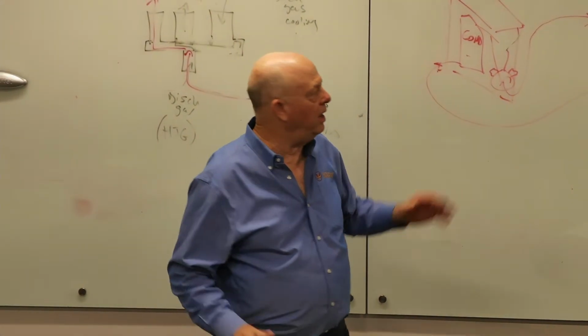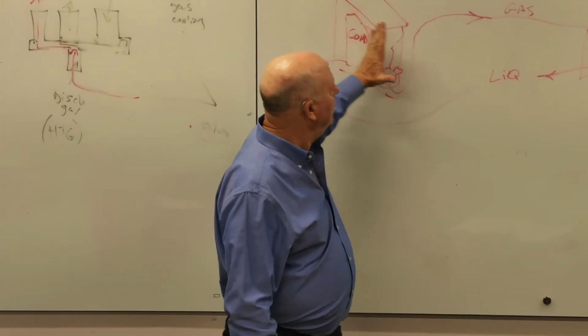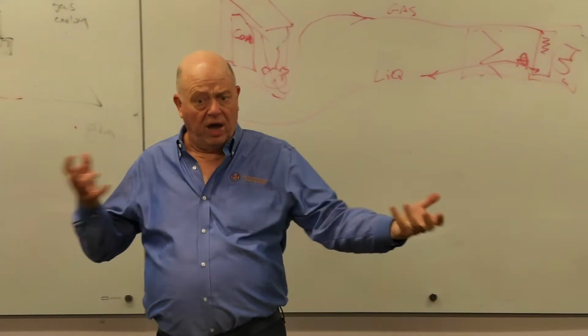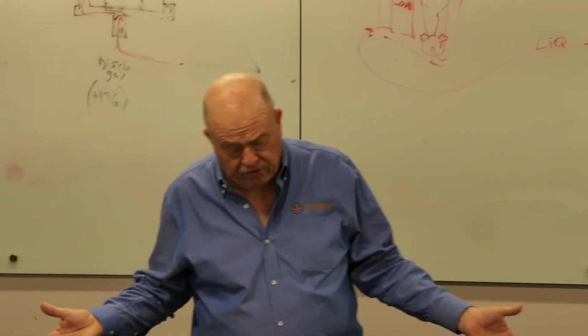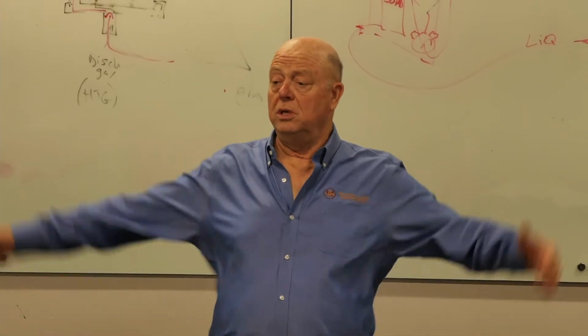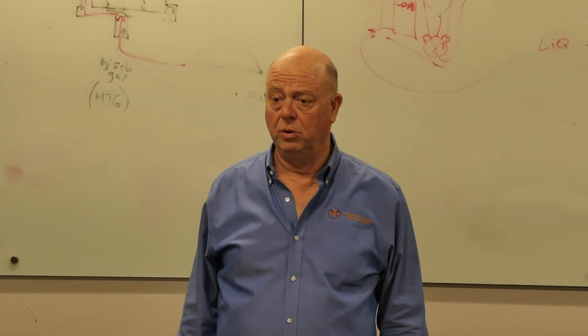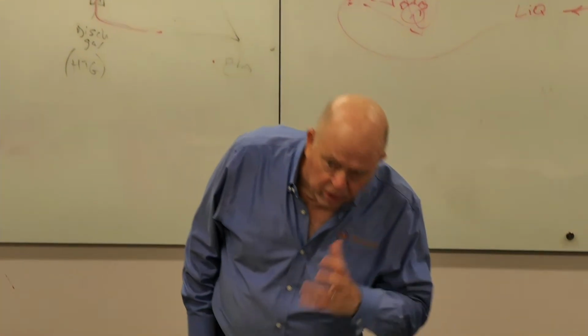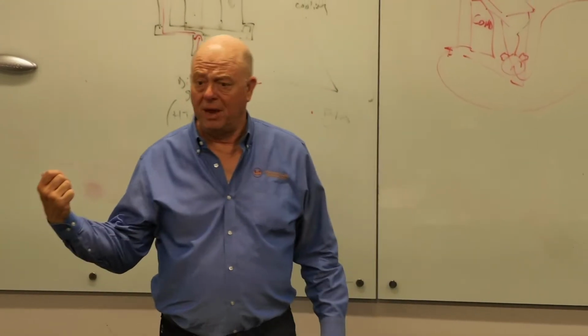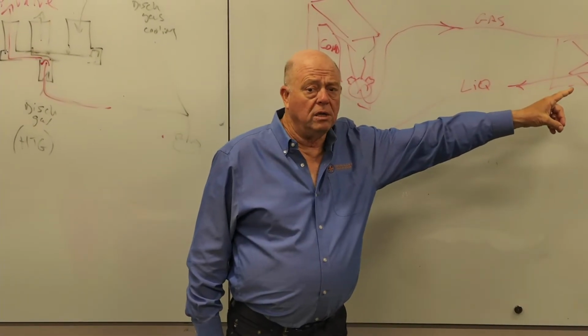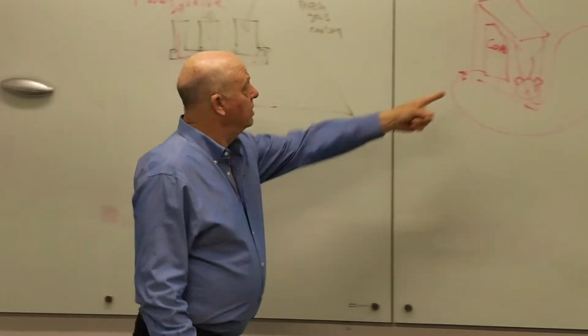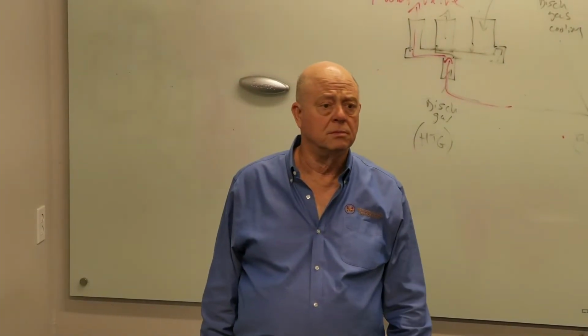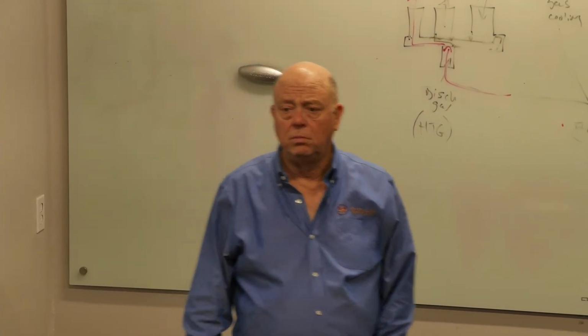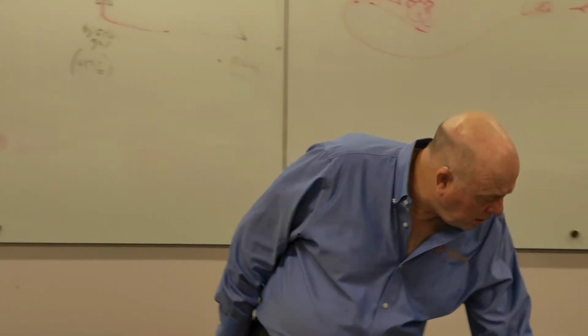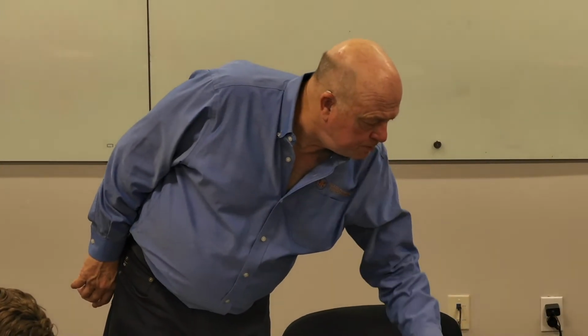When you're doing a heat pump system, that coil and this coil have got to be designed for each other. Now you could do it manually in a big built-up system if you knew what you were doing. But what is recommended and what most people do is they buy from the manufacturer an air handler, at least the coil, if not the whole air handler, that's paired for the condensing unit. That's what we do. Okay, that got us through heat pumps.